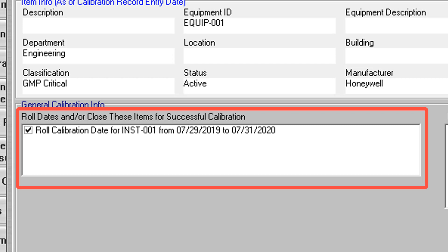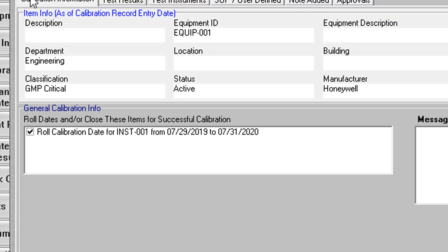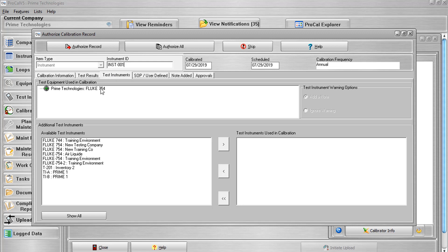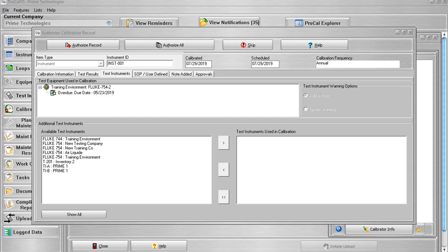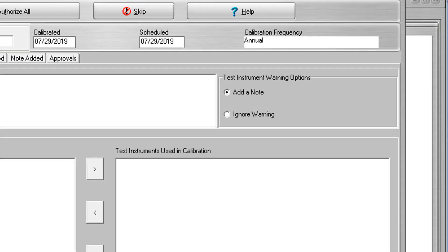The Roll Dates and/or Close These Items for Successful Calibration checklist operates exactly the same as the checklist on the calibration screen. The user is required to check the updates they would like to apply if the calibration passes. The test instruments tab contains a list of test instruments used for the current calibration, and there may be associated warnings for each listed item. The warning condition is indicated by the color of the icon: green means no warnings and the item will be added; yellow means warnings are possible but the item will be added anyway; and red means either the item does not exist or warnings prevent it from being added. You can also choose to add a note for the warning or ignore the warning for this calibration record by highlighting the test instrument and using the radio buttons to the right.